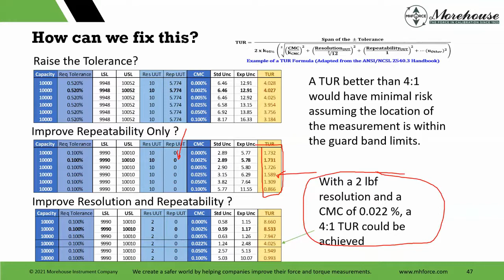How do you fix it? You need to figure out a way to lower the uncertainty and adjust acceptance limit to limit lower and upper risk to less than 2%. Now, this is just, like I said, pretty much standard on a PFA. You might not be able to accept the 2% risk. So if that's the case, you just need to have that discussion with your cal provider. So right here, take more measurements, repeatability. This just shows here standard uncertainties. And again, TURs and risk.